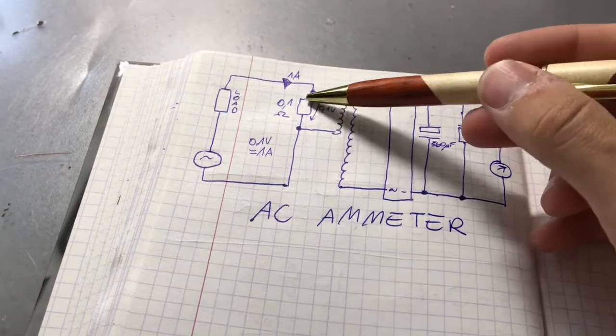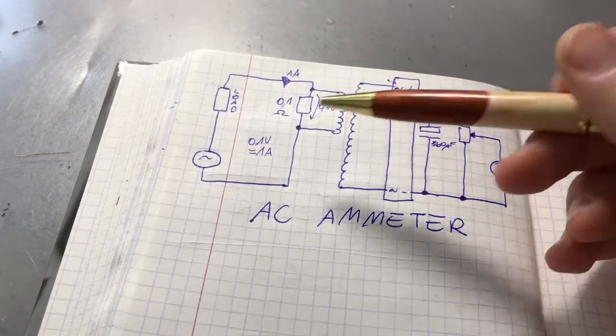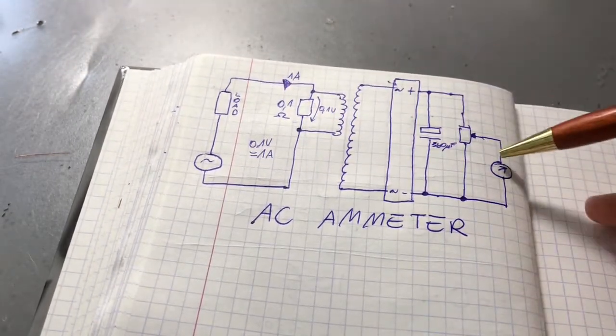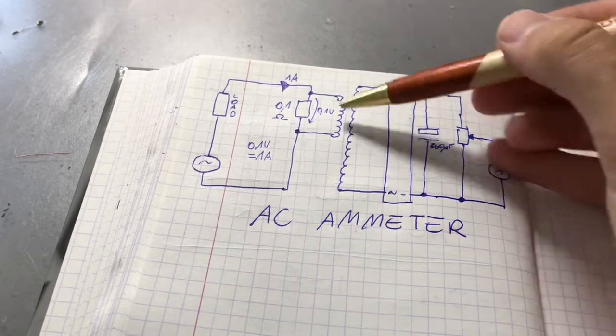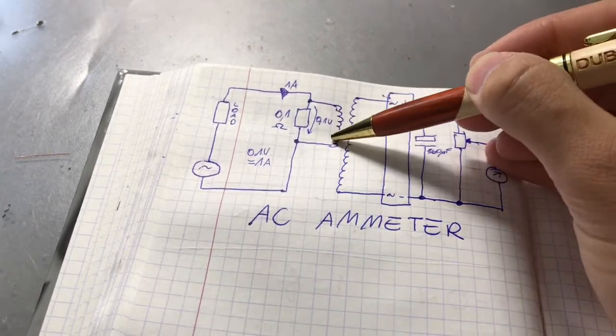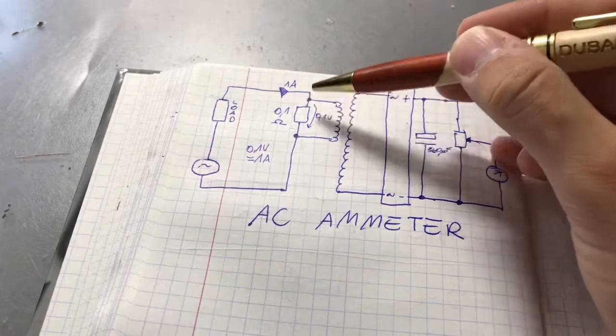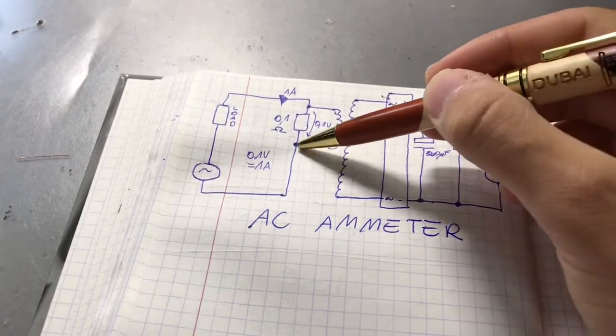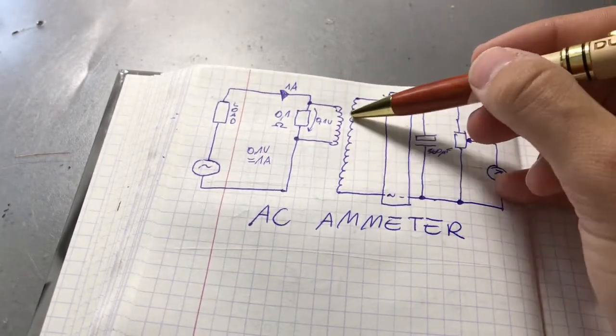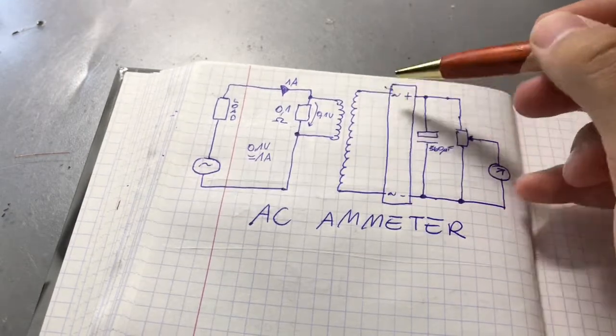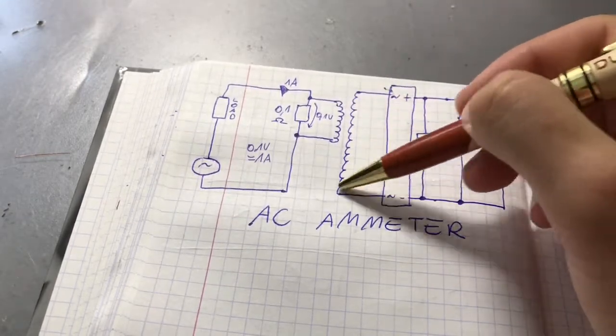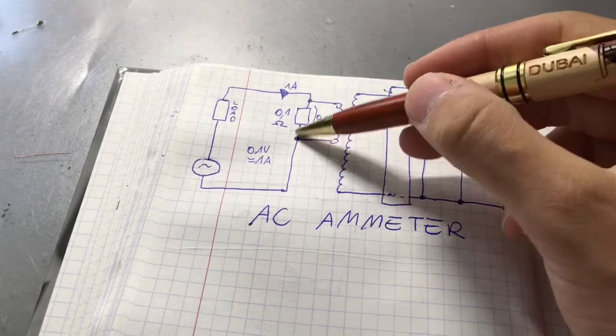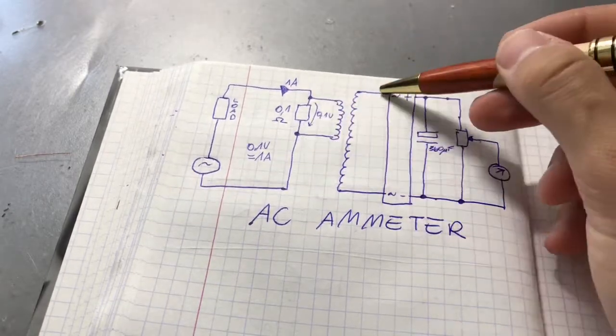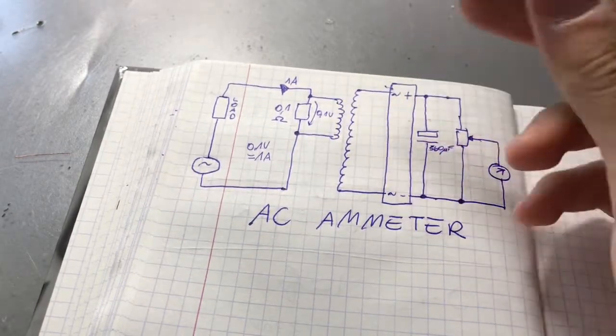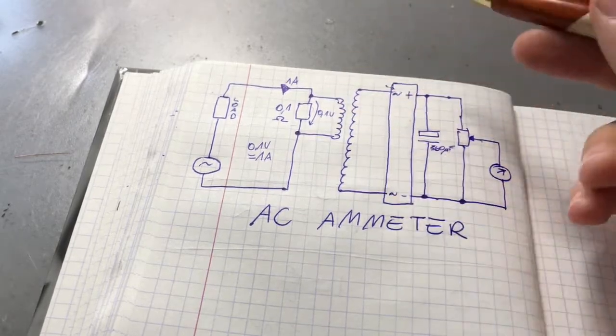But this is too low a voltage to do anything useful with it, to drive an analog movement, for example. So we have some kind of 5 or 6 ohm winding across here, which bumps up the voltage. Then the transformer bumps up the voltage again. On the primary we have the voltage that is across this shunt, and on the secondary we have this voltage but bumped up like 10 or 100 times.